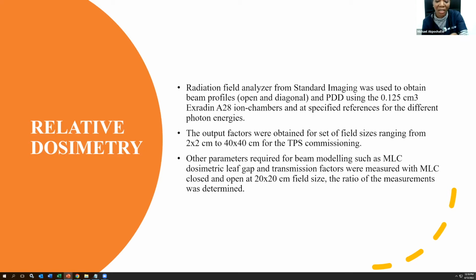So we acquire the PDD using the Exradin A28, that is the pinpoint. It has 0.125 cc. Now, we have specified references for different photon energies. There are some other things we actually acquire apart from the beam profiles, the PDD and the output factors, such as the MLC leaf gap and the transmission factors. Now, this is carried out at 20 by 20 field size.